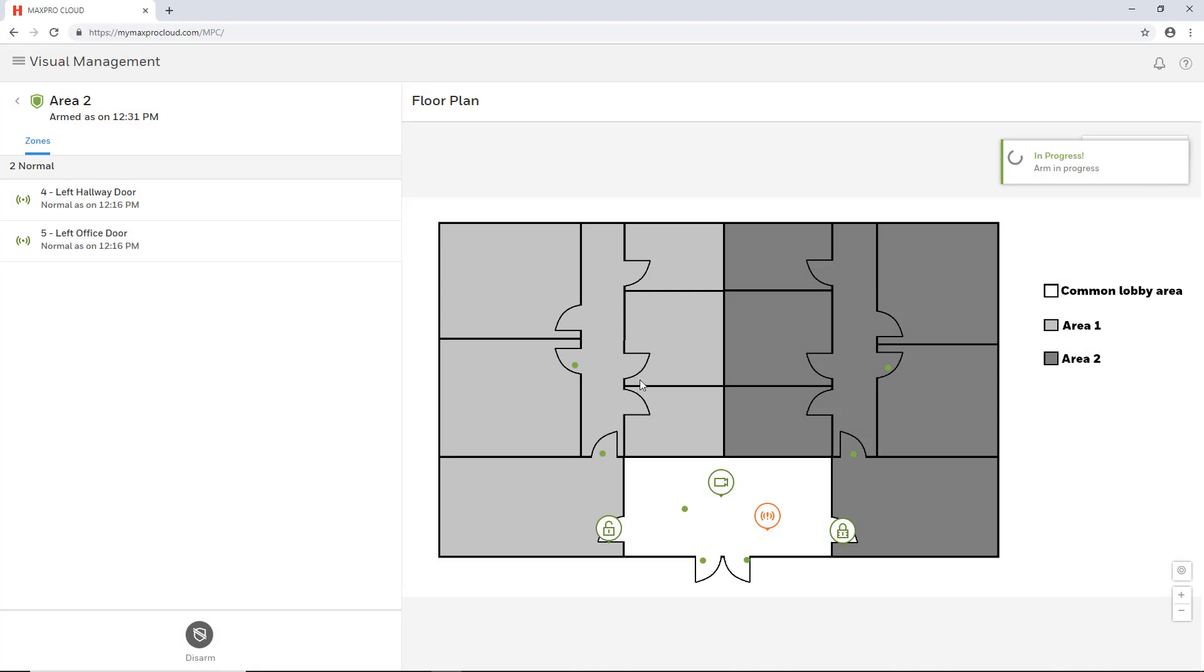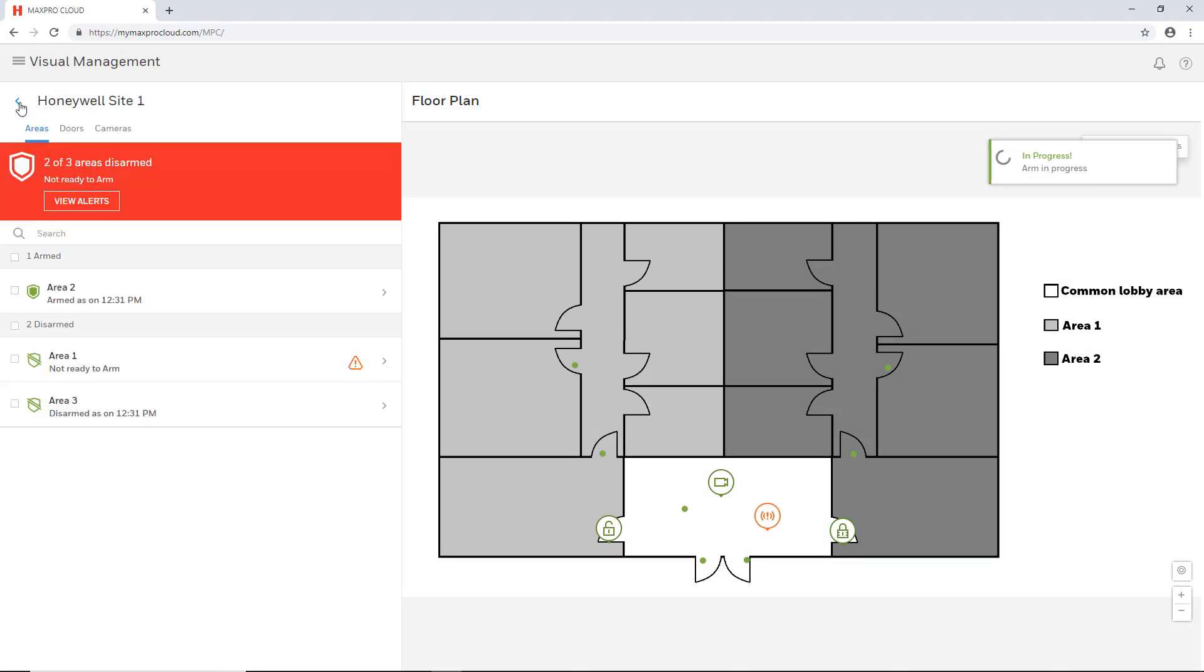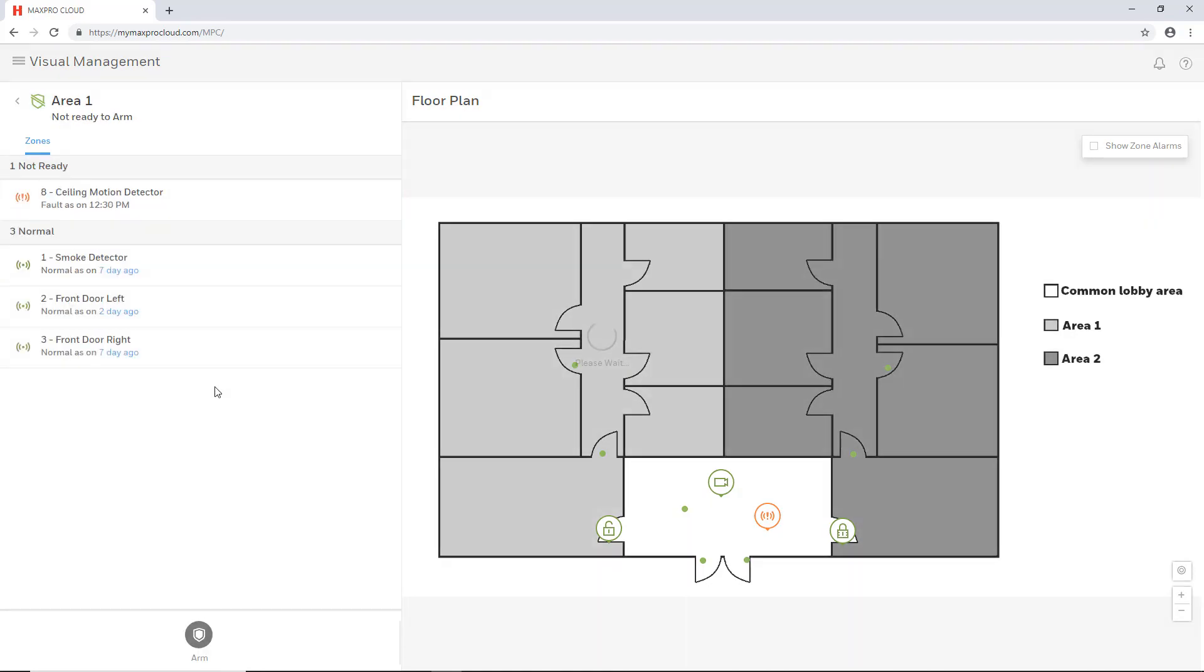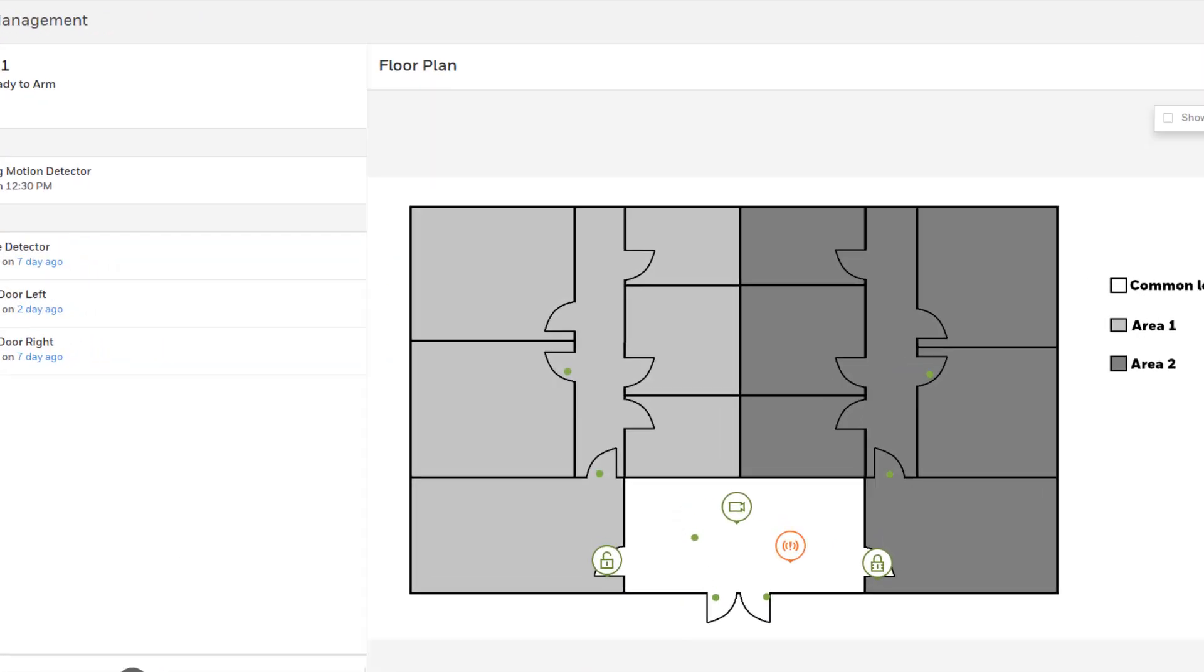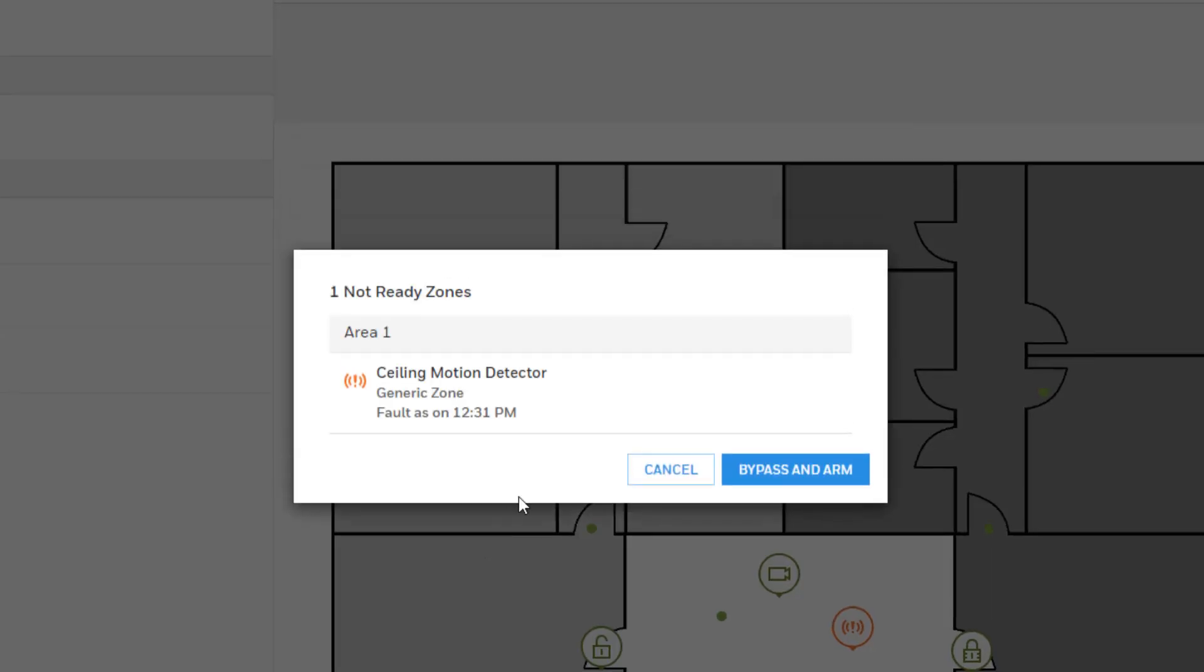If you are attempting to arm an area and there are faulted zones within that area, you will instead get a window listing all the faulted zones and the option to bypass those zones and arm the area.